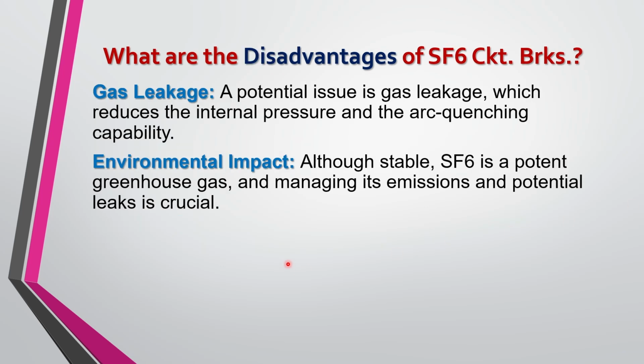Now, SF6 circuit breakers also have a few demerits or disadvantages. Gas leakage is a problematic area. A potential issue is gas leakage, which reduces the internal pressure and the arc quenching capability of SF6 circuit breakers. Environmental impact. Although SF6 is a stable gas, SF6 is a potent greenhouse gas as well. And managing its emission and potential leaks is crucial. So that's a challenge when you are using an SF6 circuit breaker.